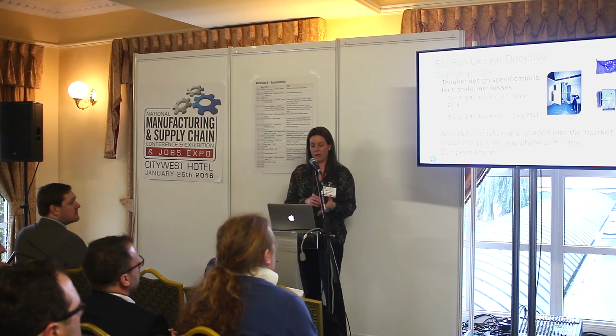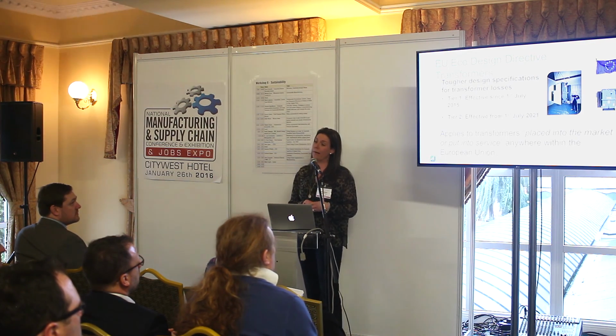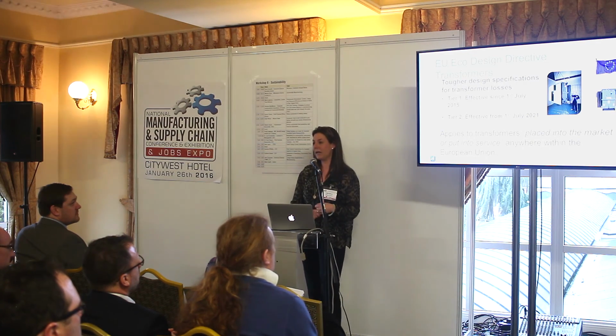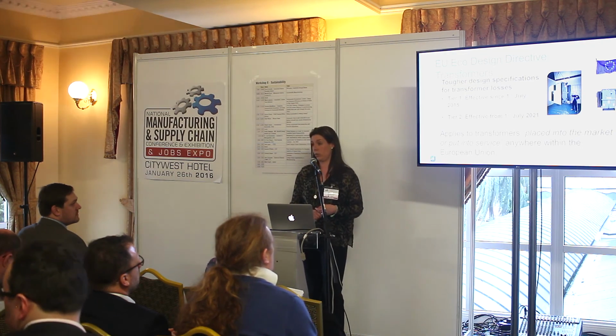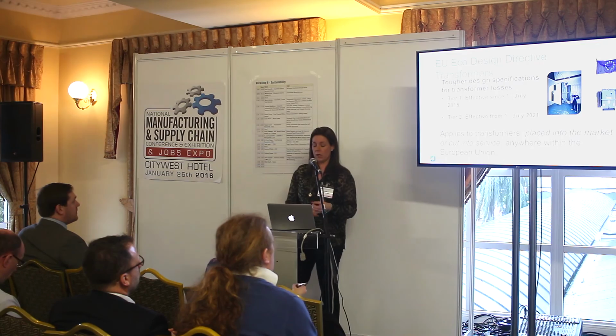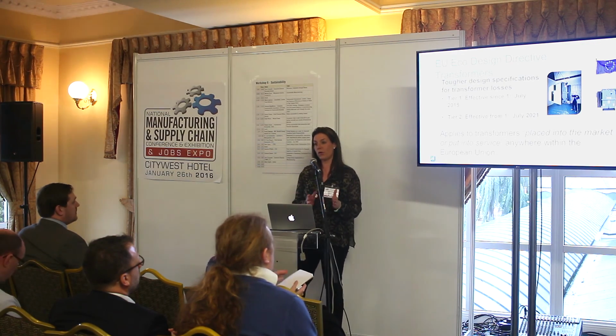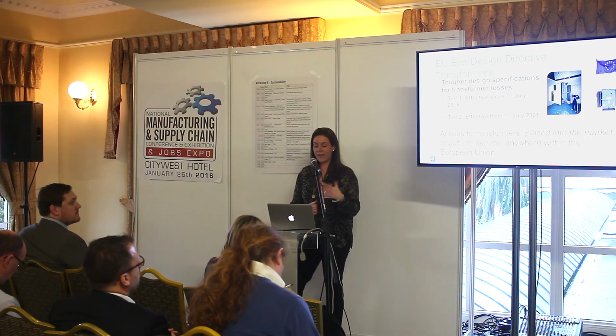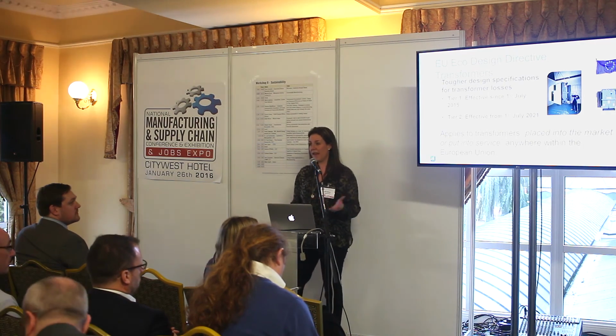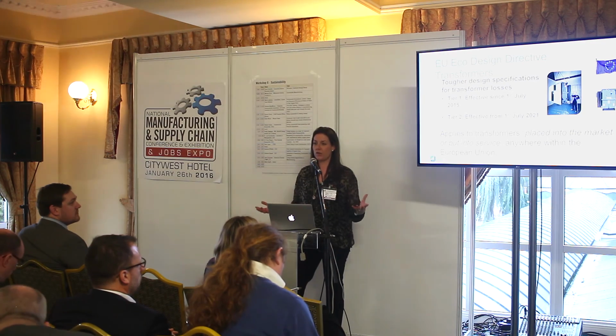What's happened is the EU Eco-Design Directive was brought around, and the first tier was last July. The aim was to prevent the installation of high-loss transformers across the energy network. So they've got two tiers - tier 1 was July last year, and then there's a second tier which asks to reduce the transformer losses further, effective from July 2021. The actual directive applies to transformers placed in the market or put into service anywhere within the European Union, so it's an extremely broad piece of legislation.